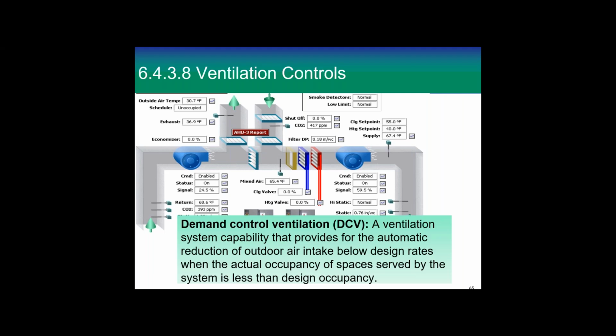Now, this is very important, and you have to believe me, because I have people argue with me sometimes. I promise that we, as the energy people, would never say we're going to have demand control ventilation so that you know when to increase the amount of air into the space. When you design to ASHRAE 62 and you put the amount of air you're supposed to put in by ASHRAE 62, you as an engineer are never required to add more than that to meet your safe building. If you decide to, that's your business, but you don't have to do that.